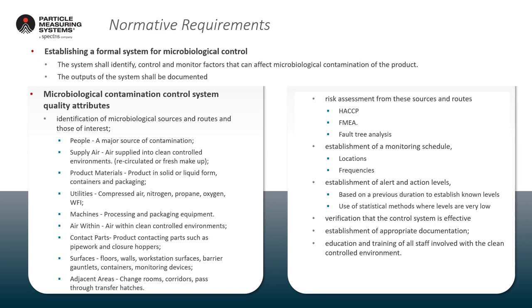The normative requirements want to define what's required in establishing a formal system for microbiological control: defining the microbiological contamination control system's quality attributes, the identification of microbial sources and routes of interest, the risk assessment to see how those sources are generated and their routes into critical areas, the establishment of a monitoring schedule, the establishment of alert and action levels, verification that control systems are effective, and documentation, education and training.